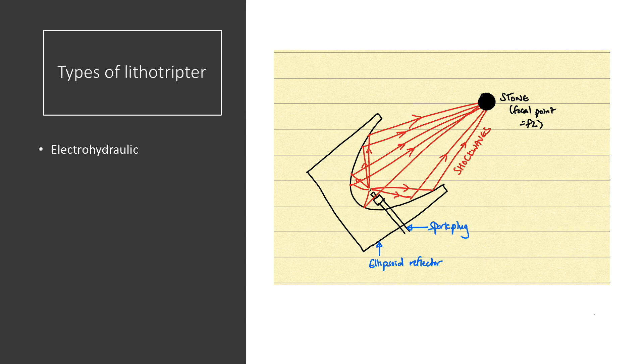However, the energy generated can be quite high, and the focal zone at the stone can be a bit wider than with more modern lithotriptors. One of the other disadvantages of the EHL device is that the spark plugs have a limited lifespan and may need to be replaced continuously.